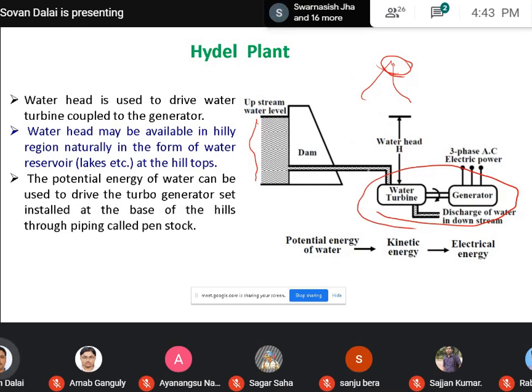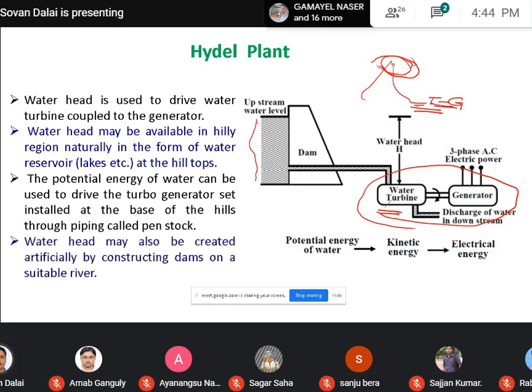So what is the principle behind that? The potential energy of the water can be used to drive the turbo generator set installed at the base of the hill. So the turbine generator set is placed at the base of the hill. Suppose the natural lake or the artificial water reservoir is at the hilltop, and the turbine and generator set are placed at the bottom, or base, of the hill, connected through piping. That arrangement is called the penstock. This water head may also be created artificially by constructing a dam on a suitable river.